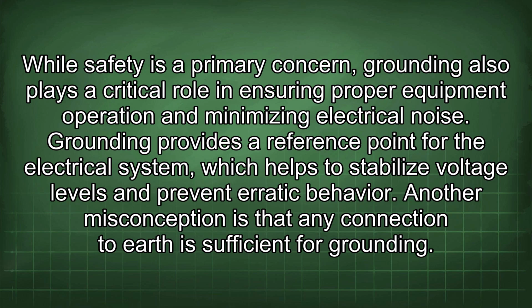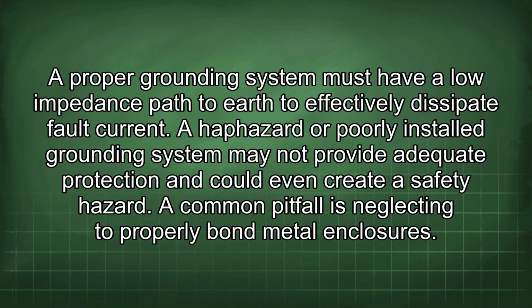Another misconception is that any connection to earth is sufficient for grounding. A proper grounding system must have a low impedance path to earth to effectively dissipate fault current. A haphazard or poorly installed grounding system may not provide adequate protection and could even create a safety hazard. A common pitfall is neglecting to properly bond metal enclosures.